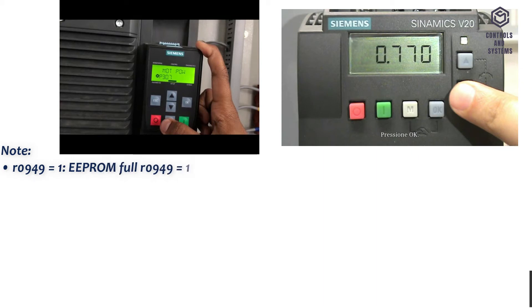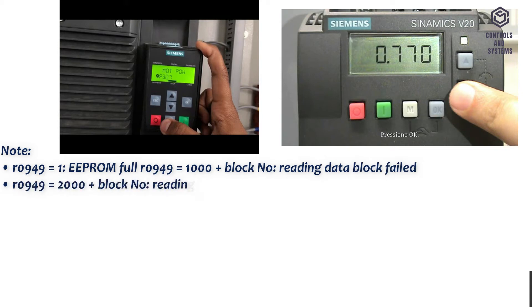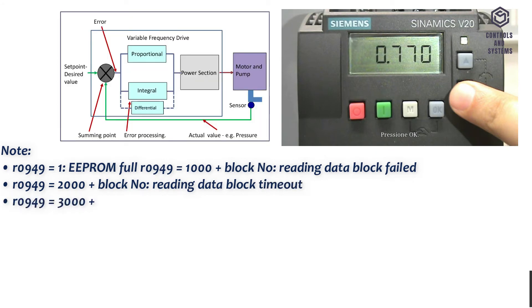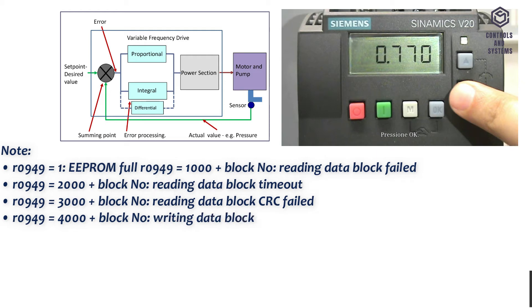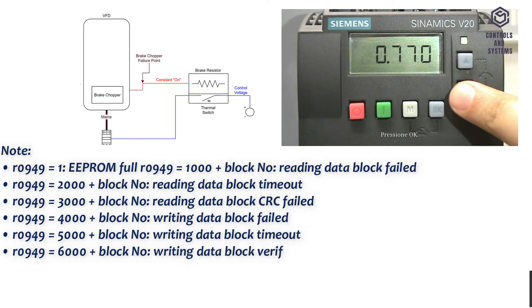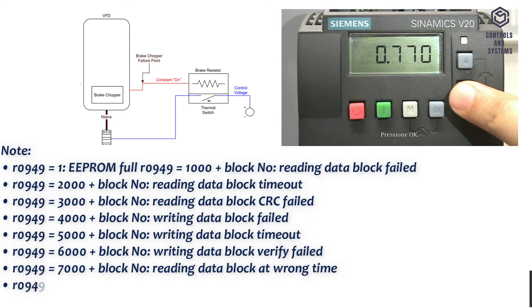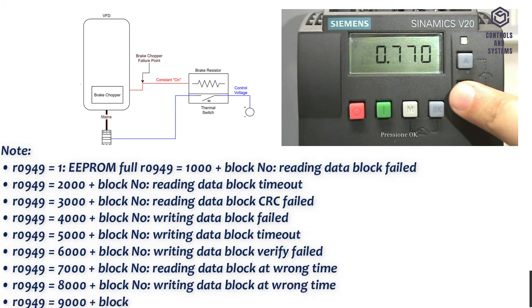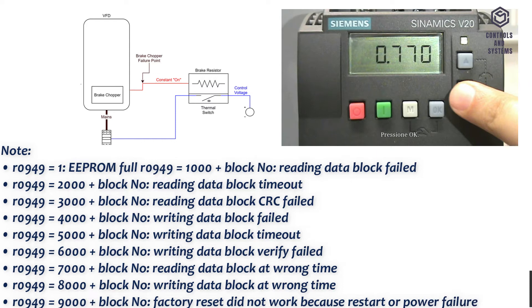Note: R0949 equals 1: EEPROM full. R0949 equals 1000 plus block number: reading data block failed. R0949 equals 2000 plus block number: reading data block timeout. R0949 equals 3000 plus block number: reading data block CRC failed. R0949 equals 5000 plus block number: writing data block timeout. R0949 equals 6000 plus block number: writing data block verify failed. R0949 equals 8000 plus block number: writing data block at wrong time. R0949 equals 9000 plus block number: factory reset did not work because of restart or power failure.